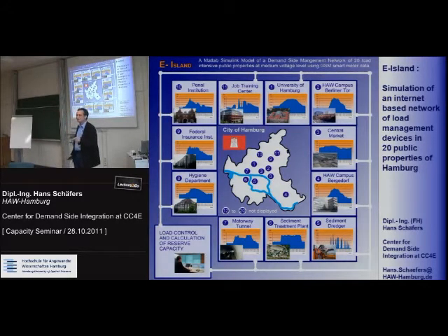Now, if you could use, without the emergency ventilation, still use all the ventilation that they have installed regularly, then that would range up to 5 megawatts, or basically 3.5. And the rest, the 1.5, would come from the central market, where there's lots of cold storage actually running that you could use to actually take up more energy, produce more cold, and then later on you don't have to produce the cold, right? So that's okay, this one, because it's really energy storage. You take up more electricity, and then in a couple of hours you don't need to take it up.